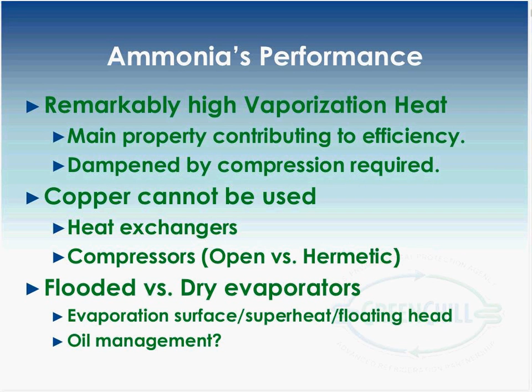And with a flooded chiller, you can float the head a lot easier than you can with the direct expansion system. So with the flooded evaporator, it's got a more mild expansion, which makes it easier to float the head pressure down and get a lower pressure on the liquid side. I put oil management there because the service demands are a little different with the dry evaporator versus the flooded evaporator. But we don't really go into that right now because it doesn't have a lot to do with the performance.